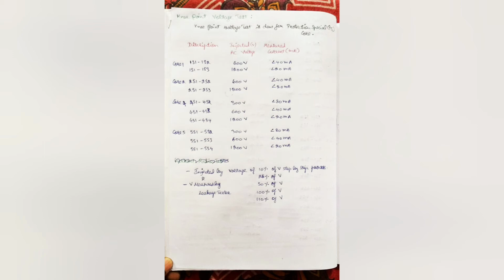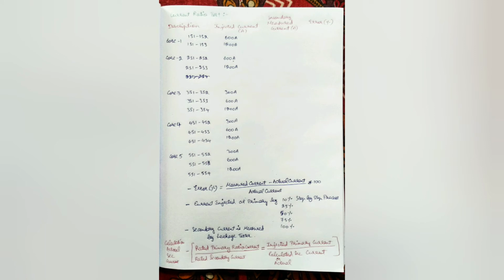So while doing the knee point voltage test, the secondary side will be in open condition only. Because we are going to inject the voltage on the secondary core only, on the primary we don't need to do any shorting or anything. We inject the voltage on the secondary side, and we measure the leakage by using an ammeter or a tong tester at the time of injection, and the leakage should be less than the predefined or factory value. By this testing we define the saturation level of your CT, and the saturation curves are also obtained. Next, coming to the ratio test.